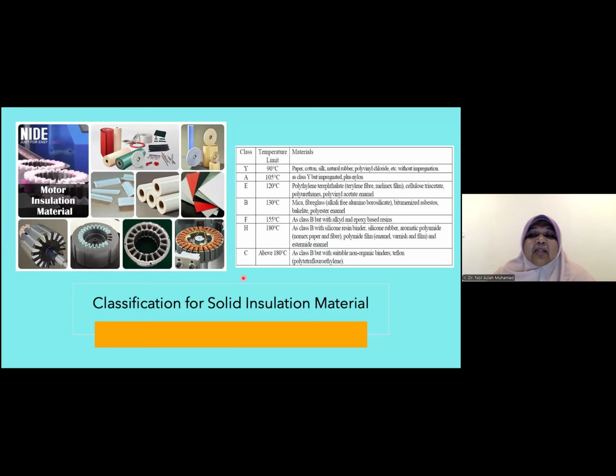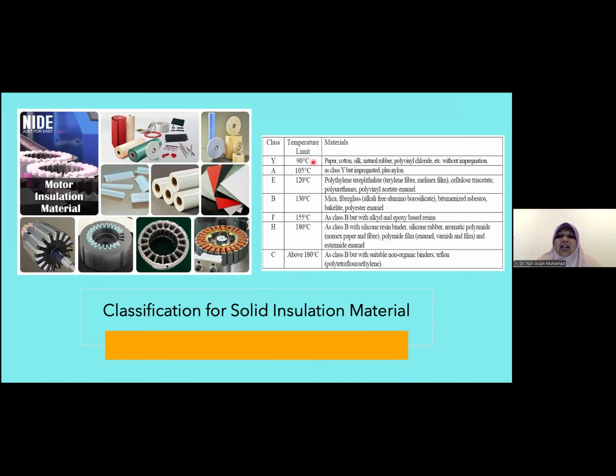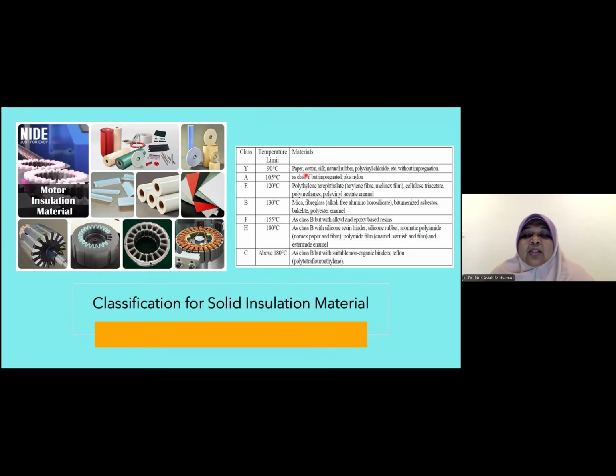The classes depend on the temperature, the operating temperature that they can withstand. So there is paper insulation, which is classed as Y. There is class A, which is also paper, but with nylon impregnated with oil or other materials. Then we have class E, which is 120 degrees. We use polymer, which is polyethylene. We have cellulose. Then we have class B that can operate up to 130 degrees. We have mica, fiberglass, asbestos. Then we also have polyester enamel.